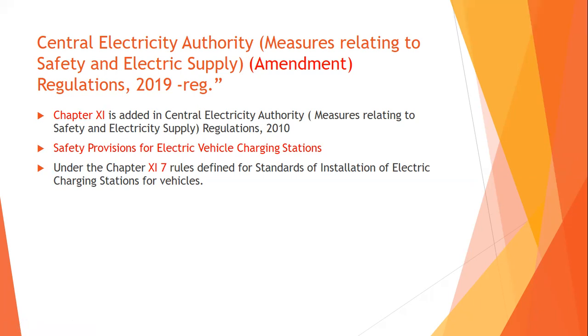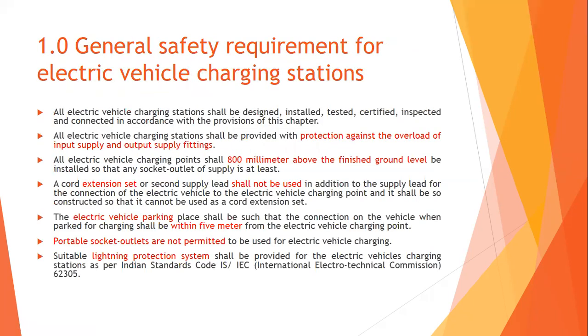Rule 1 covers general safety requirements for electric vehicle charging stations. All electric vehicle charging stations shall be designed, installed, tested, certified, inspected, and connected in accordance with the provisions of this chapter. All EV charging stations shall be provided with protection against overload of input supply and output supply fittings — whether AC or DC — with MCBs or protected circuits.